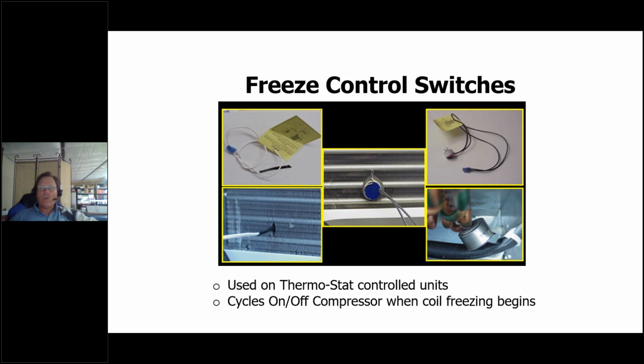Well, that compressor is pounding away, going to try to make this thing happen, try to get things going, but there's no airflow across those coils because they've iced over, or they're not getting an airflow because the filters are clogged. So what the manufacturers did is they put a freeze control, and basically all they're doing is putting a little sensor in the fins measuring for ice. When they begin to start getting ice, that little sensor senses that ice, and it reaches over and turns off the compressor, tells the fan to keep going, but it turns off the compressor, so we're not moving refrigerant. And in a short period of time, the fan keeps running just like you'd had a hair dryer up there, and pretty soon you thaw that ice out, and then the freeze control senses that the ice is gone, and now it turns on the compressor for you.